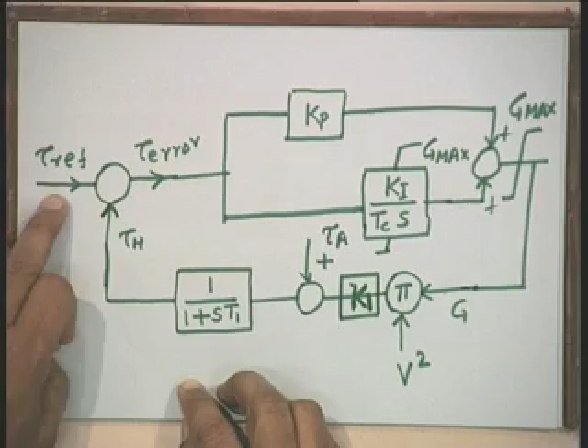Now under steady state conditions, tau reference equals tau h. If you make this substitution in this differential equation and put the derivative term to 0, then we can write tau reference equal to K1 times V naught squared G0 plus tau A. That is the reference temperature setting which is required to attain the required value of tau h, where the constant K1 is equal to tau reference minus tau A divided by V0 squared G0. With this, I have briefly introduced how a dynamically controlled or thermostatically controlled load can be represented. These differential equations are to be written along with the system differential equations.